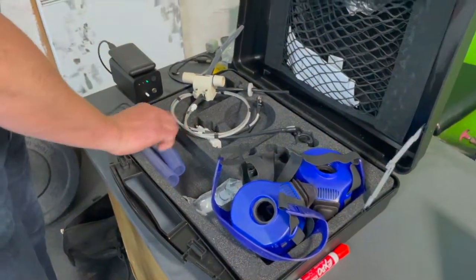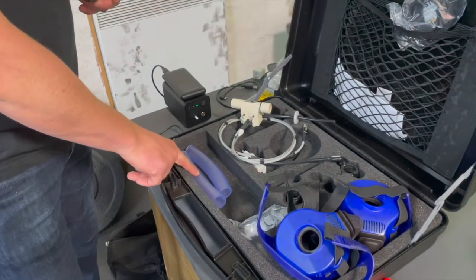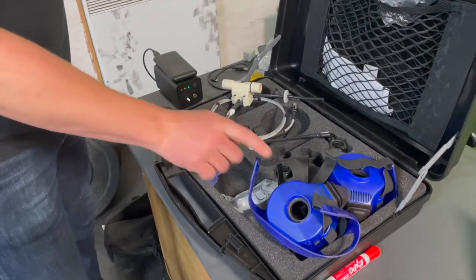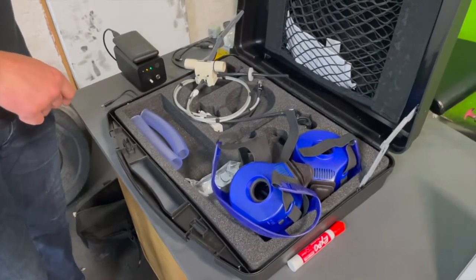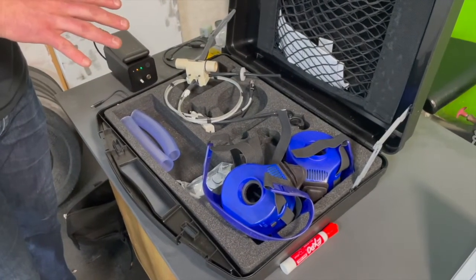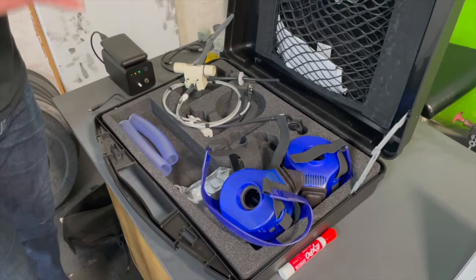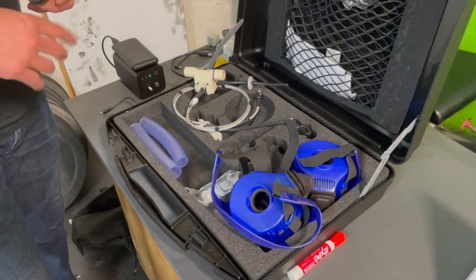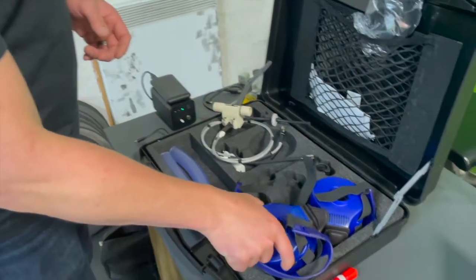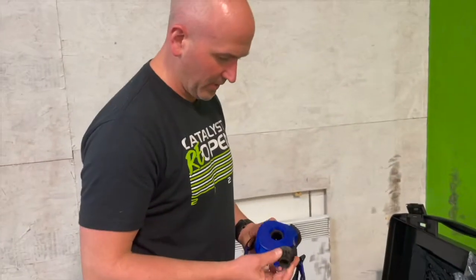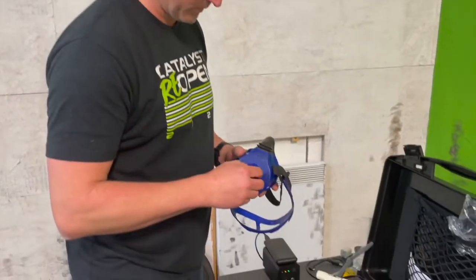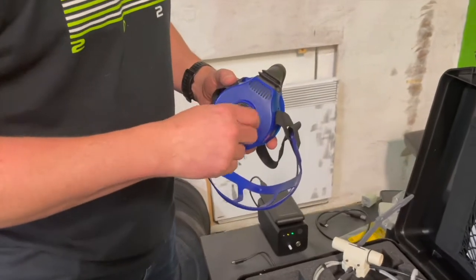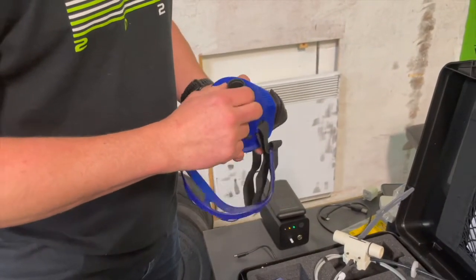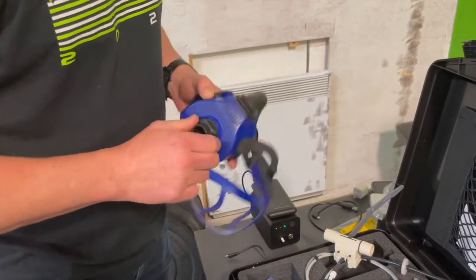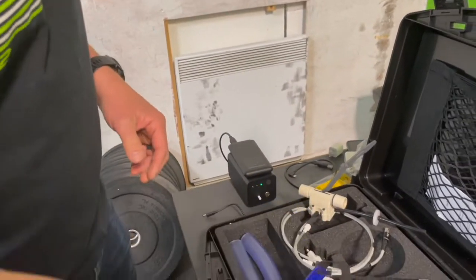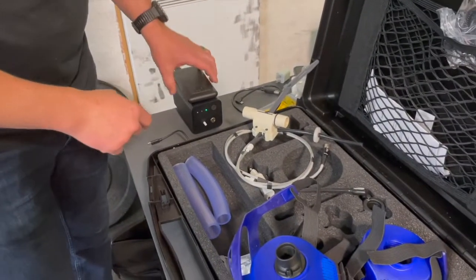There are also some cleaning tubes here. We'll go through a little bit of a cleaning tutorial later. We do have to clean the mask and the flow sensor between each test. We've got some chemicals to use for that, and there is a really simple to follow process for that. So what I'm going to do right now is start by putting Chris's mask together. We're going to insert that adapter into the mask until it's nice and snug. You don't have to over tighten it, but it should be nice and tight. And then we are going to connect the flow sensor to the PNOE.